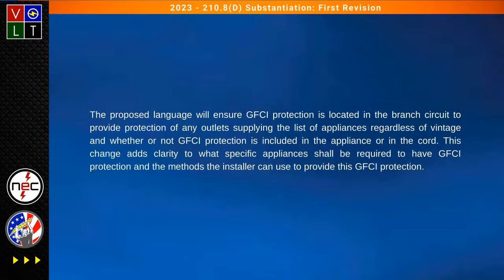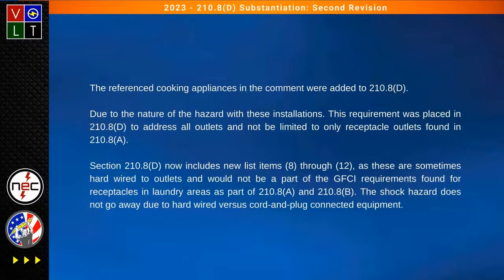Well, watch the second revision that they do. Now this is where it gets fun. It says the referenced cook appliances in the comment were added to 210.8D. Now it says, due to the nature of the hazard with these installations, the requirement was placed in 210.8D to address all outlets, and not be limited to only receptacle outlets found in 210.8A. Then it says Section 210.8D now includes new list items 8 through 12, as these are sometimes hardwired to outlets. Now what does that mean right there, when it's hardwired to an outlet?